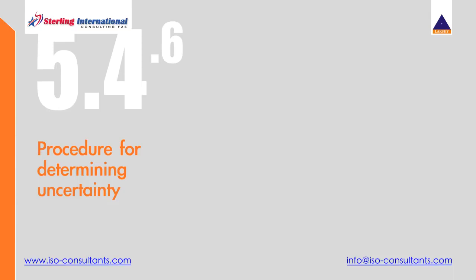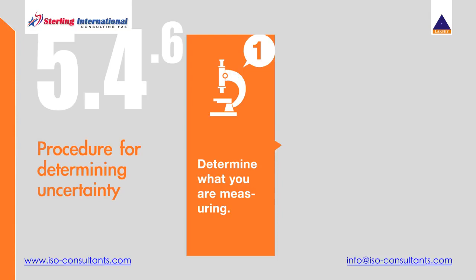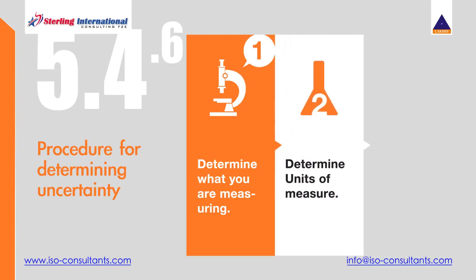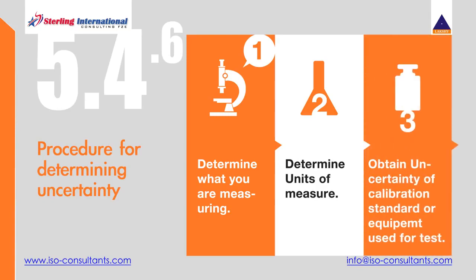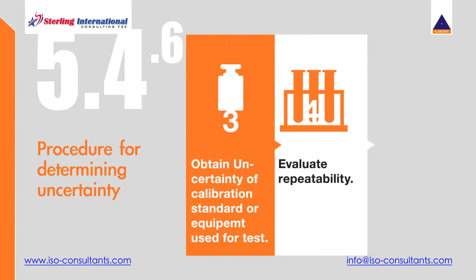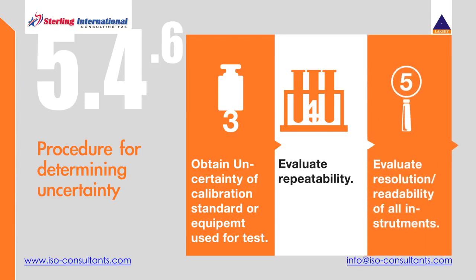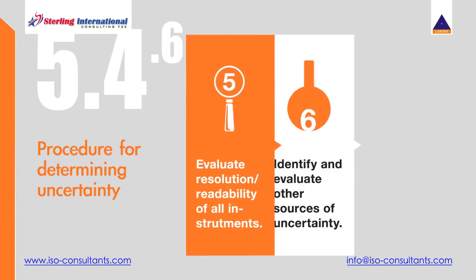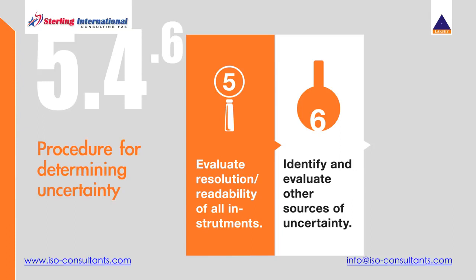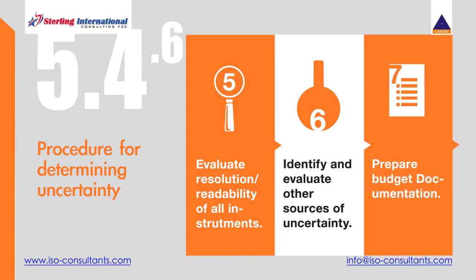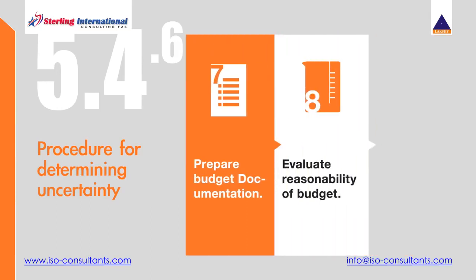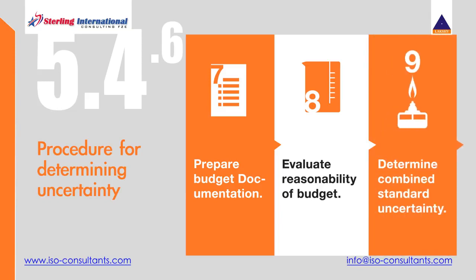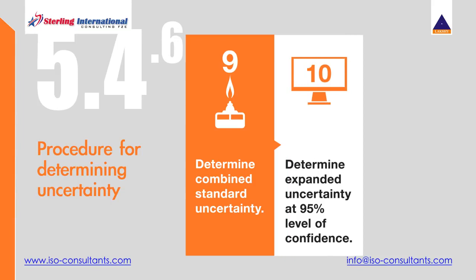Procedure for determining uncertainty. 1. Determine what you are measuring. 2. Determine units of measure, for example, feet, pounds, percentage, etc. 3. Obtain uncertainty of calibration standard or equipment used for the test. 4. Evaluate repeatability. 5. Evaluate resolution, readability of all instrumentation. 6. Identify and evaluate other sources of uncertainty. 7. Prepare budget documentation. 8. Evaluate reasonability of budget. 9. Determine combined standard uncertainty. 10. Determine expanded uncertainty at 95% level of confidence.